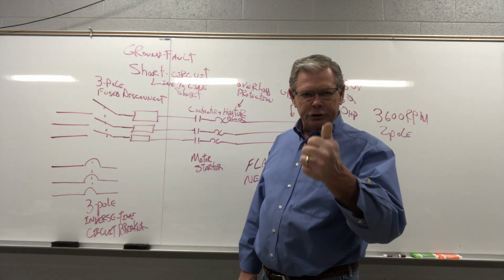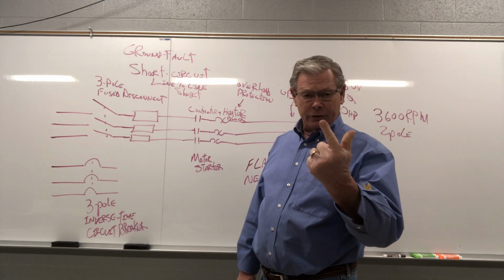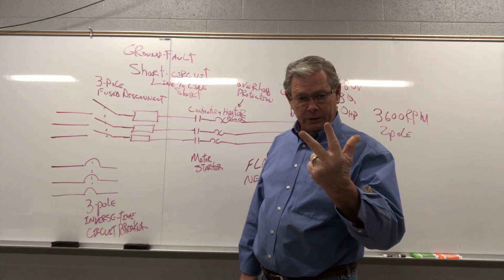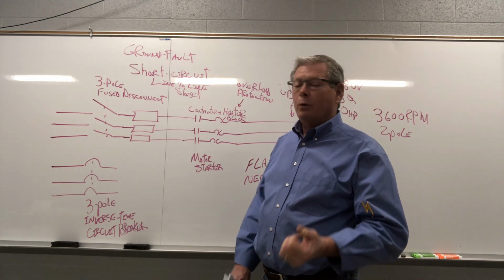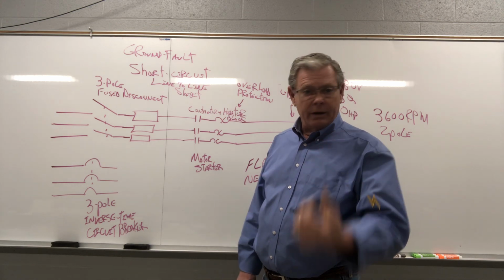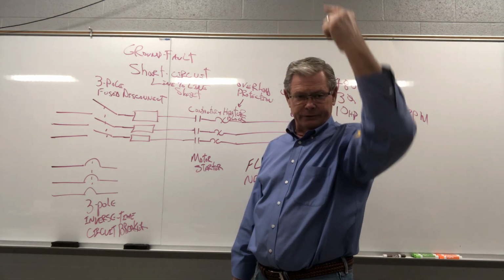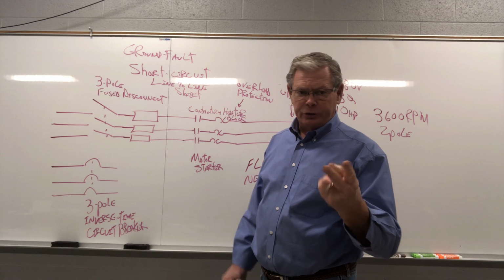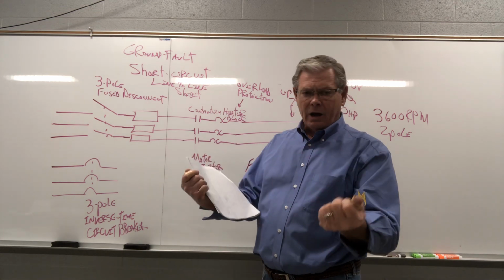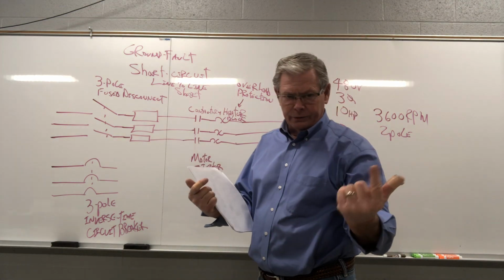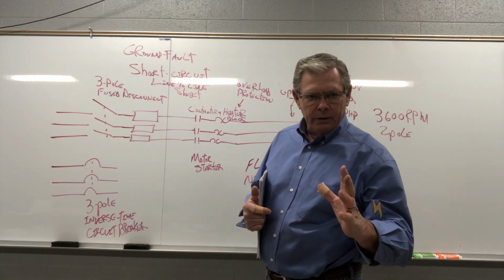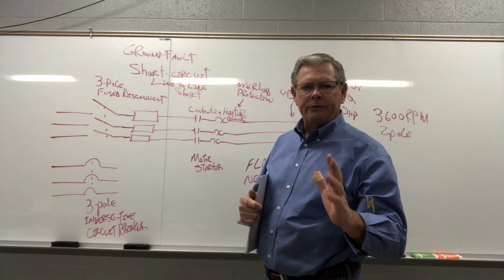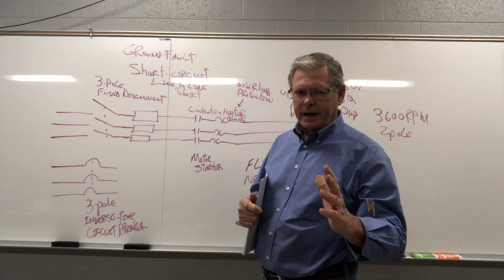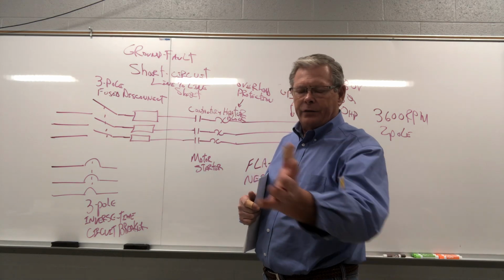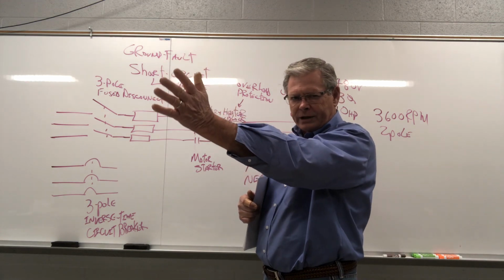Now, we have three different conditions of a circuit we have to protect from. A line-to-line short, a line-to-ground short, and overload, okay? When you have a line-to-ground short, current goes through the roof. When you have a line-to-line short, if you take an extension cord and short hot to neutral, current through the roof. Overload is when you're asking for too much horsepower off the end of that shaft. So the current for overload goes up over time.